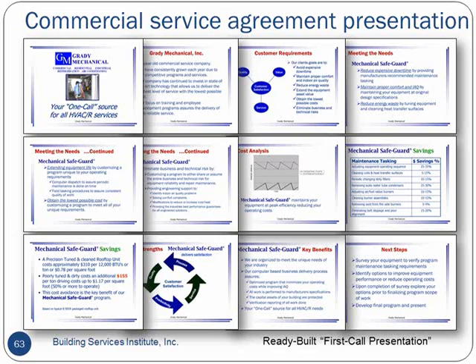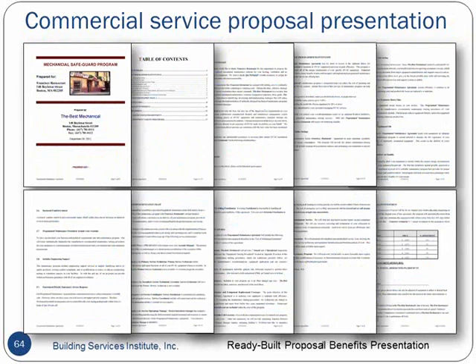The beautiful thing is that let's say you've got 30 tons of air conditioning and you can point to a number, and then you can point to this table showing the ASHRAE data says you're going to be spending up to 50% more than that because of this, and you show them the pictures of the dirty heat transfer surfaces or frost or proof that the unit's not properly charged.